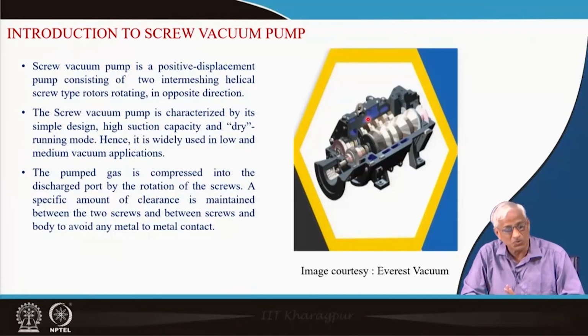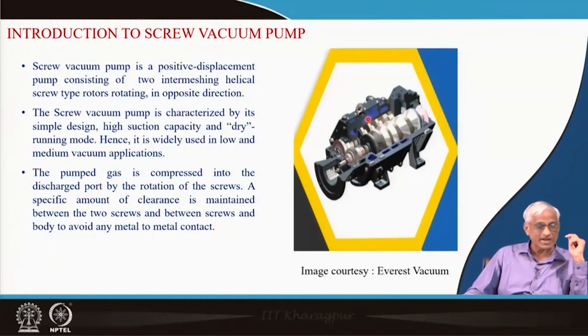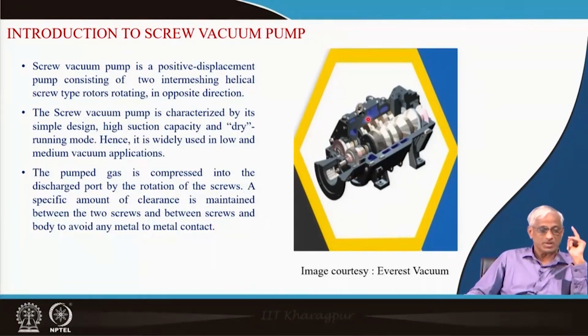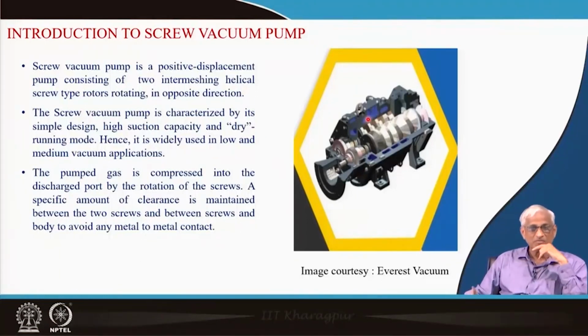Compression ratio is important, vacuum level is also important. That is why it is called a screw vacuum pump, and they are characterized by dry mode, meaning these rotors are rotating in a perfectly dry chamber. So they are very popular pumps, belonging to the dry section of medium vacuum pumps.